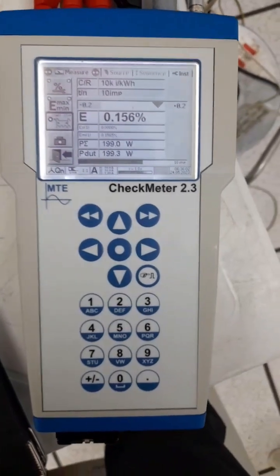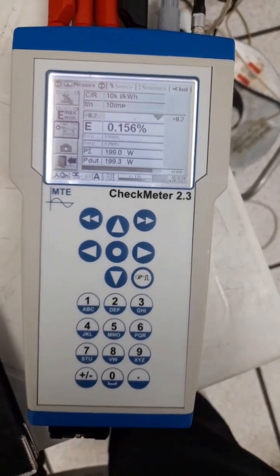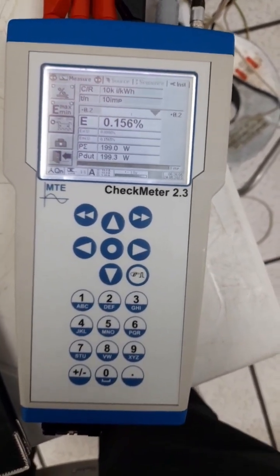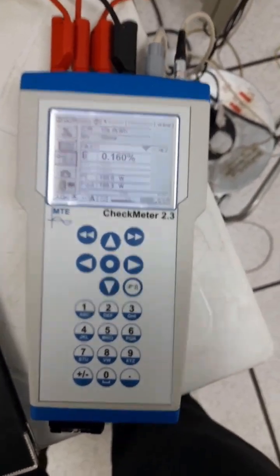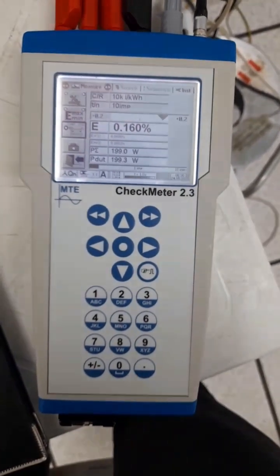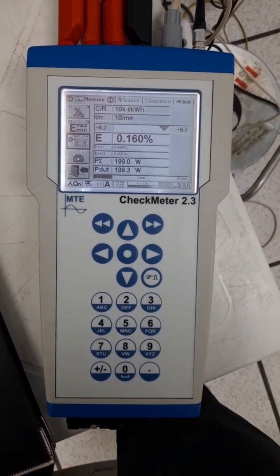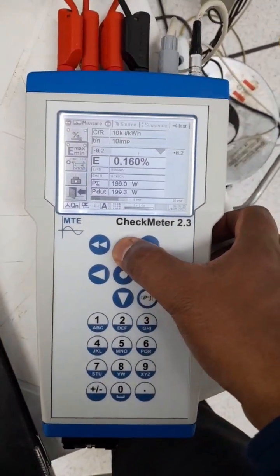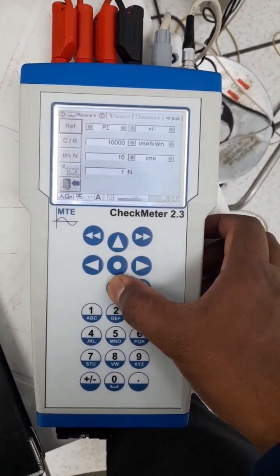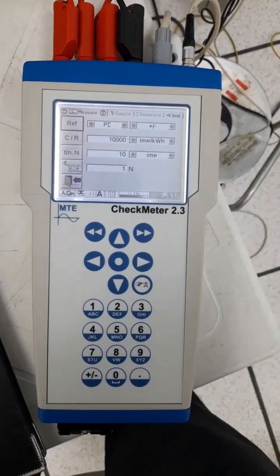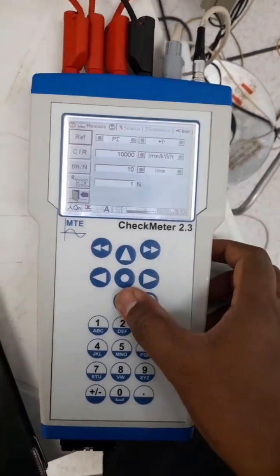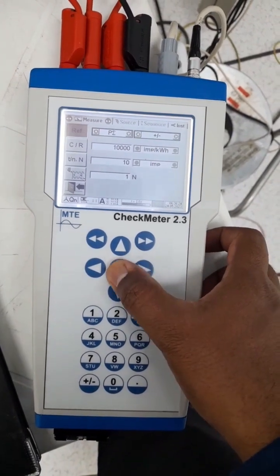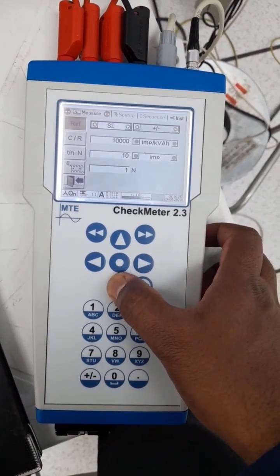I think if I adjust this scanning head again, the error may reduce. So this is how we are doing the kW. The next will be when we do the reactive power accuracy. That time you have to change this reference from P to Q.